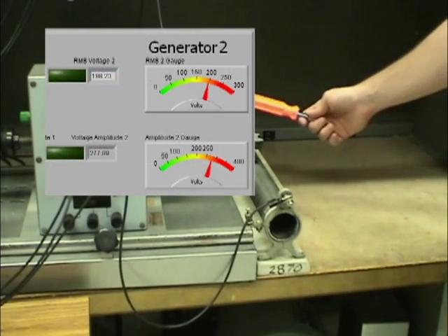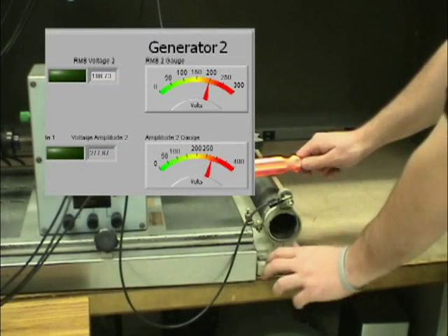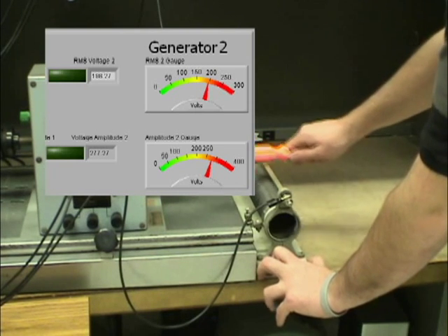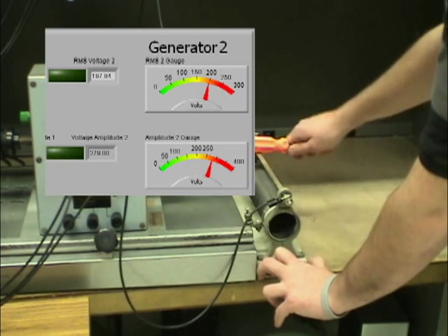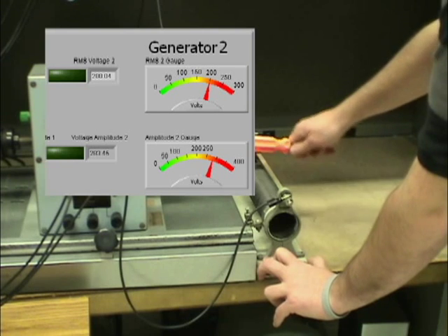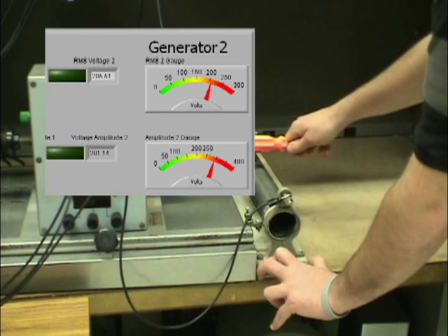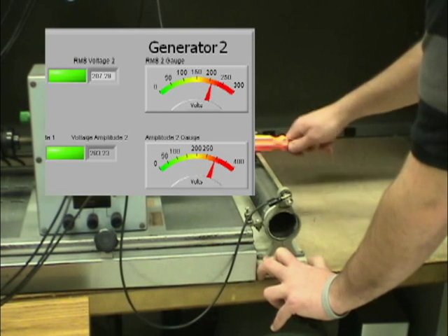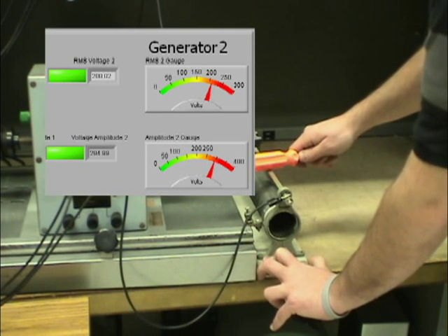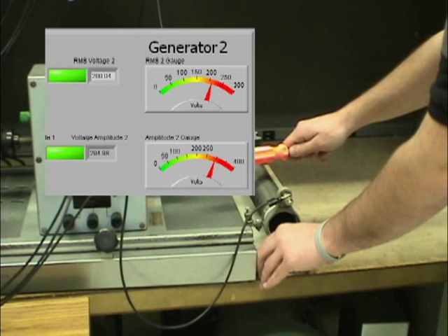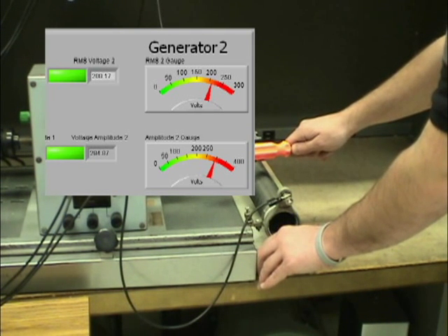Next, the voltage RMS of generator 2 needs to be adjusted to match the voltage of generator 1, and will be indicated as matched with the green light shown in LabVIEW. The closer the values are matched to one another, the more efficient the synchronization of the generator signals becomes, reducing the chance of power loss from the generators due to motoring. This will also help in the auto connection of the system.